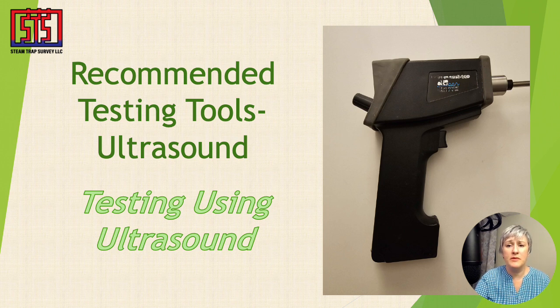Next, touch the probe downstream of the steam trap at the trap's outlet and observe the intensity levels and sound patterns. A decibel increase of 10 plus typically indicates a problem. A typical on-off trap should have a pattern of close, discharge, close. Listen for a tight shutoff. If the sound heard is a continuous rushing sound, it is most likely stuck open and wasting steam.